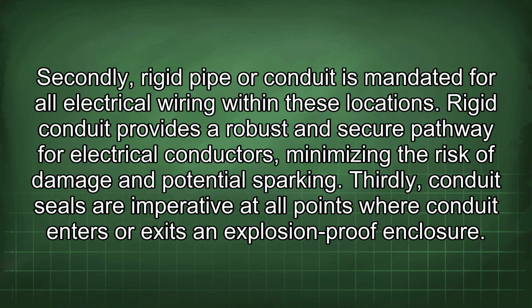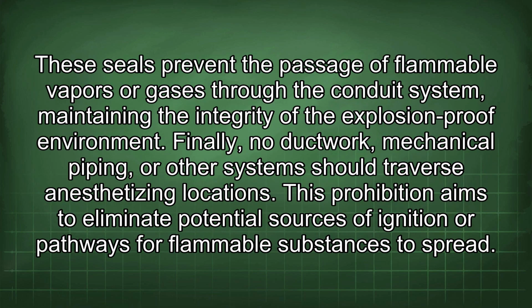Secondly, rigid pipe or conduit is mandated for all electrical wiring within these locations. Rigid conduit provides a robust and secure pathway for electrical conductors, minimizing the risk of damage and potential sparking. Thirdly, conduit seals are imperative at all points where conduit enters or exits an explosion-proof enclosure. These seals prevent the passage of flammable vapors or gases through the conduit system, maintaining the integrity of the explosion-proof environment.